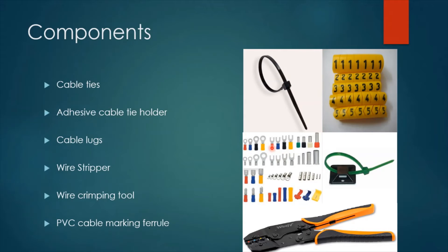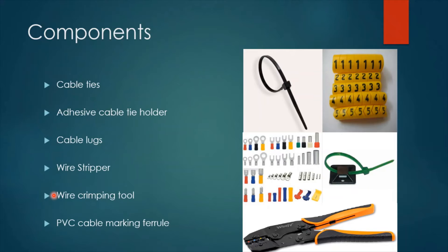Cable lugs are installed at the inside of the wire to be inserted inside the circuit breaker, and as we can see, there are different and several types of lugs. According to the terminal of the circuit breaker, you will select the most suitable lug for your case. A wire stripper tool is used to remove the insulation from the conductor, and it looks similar to the tool shown here. The wire crimping tool shown here is used to make the crimping of the lugs and to tighten the lugs within the wire.